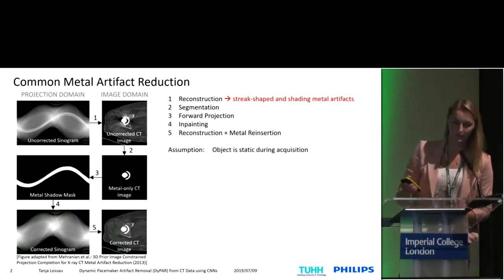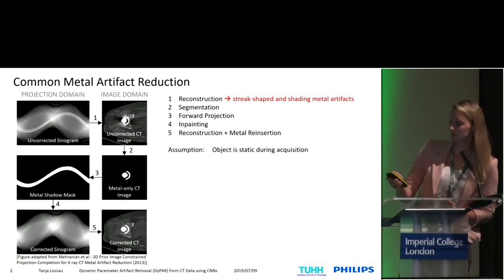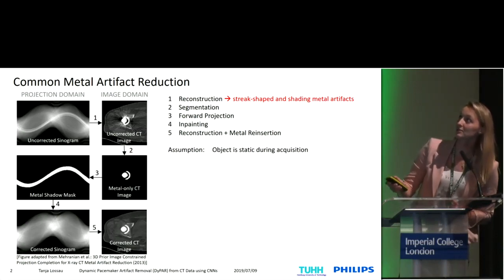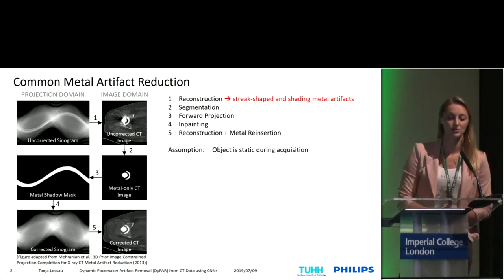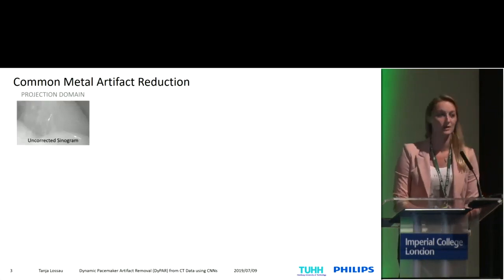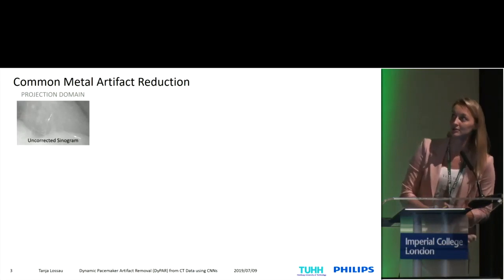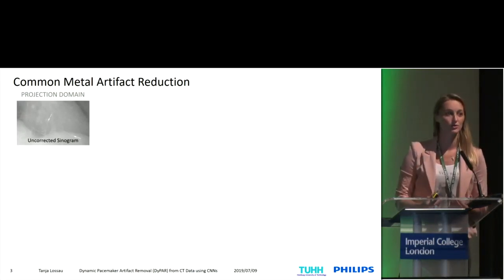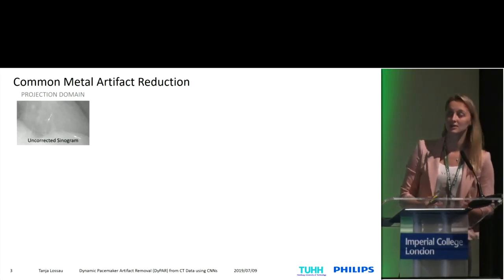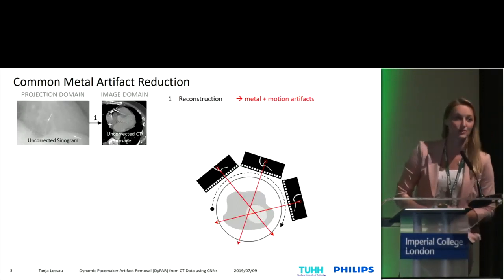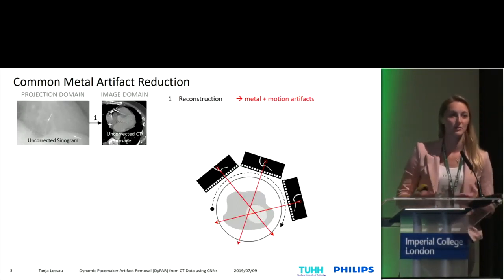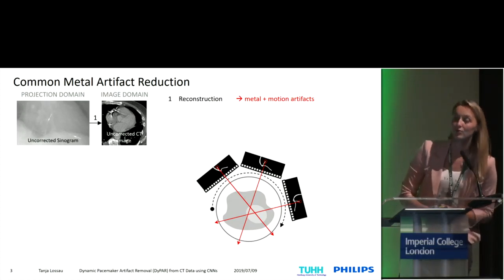So what is the problem here? The problem is that due to the metal segmentation step in the image domain, we implicitly assume that the object is static. And this is not the case for cardiac CT. When we bring motion into the pipeline and start again in the projection domain, you can see one projection view of a clinical case with an implanted pacemaker. Due to the cardiac motion, metal positions are well-defined in each projection view, but not consistent in time. When we perform the reconstruction of an image volume, all these motion states are mixed together, and we have a combination of metal and motion artifacts.